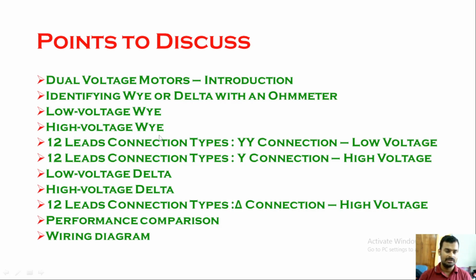9 terminals motor, and we are also going to see the 12 leads connection type with a star-star low voltage connection and star high voltage connection. Also, we are going to understand low voltage delta connection, high voltage delta connection, and the 12 leads connection type for delta connection, high voltage. And we are going to see the performance comparison when it is connected appropriately with the voltage ratings with respect to the connections made wrongly or incorrectly for the motor.